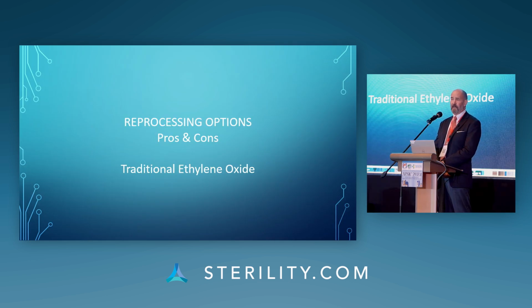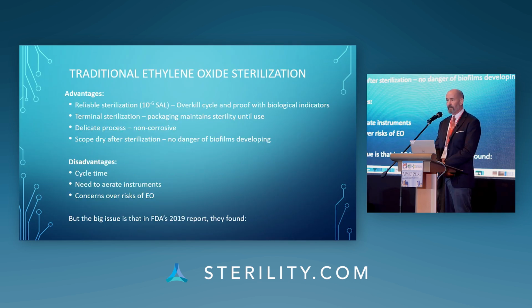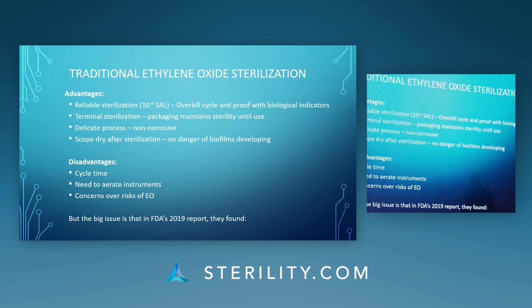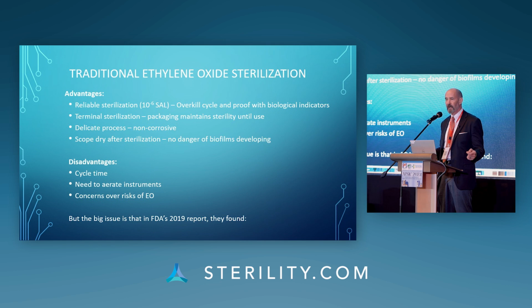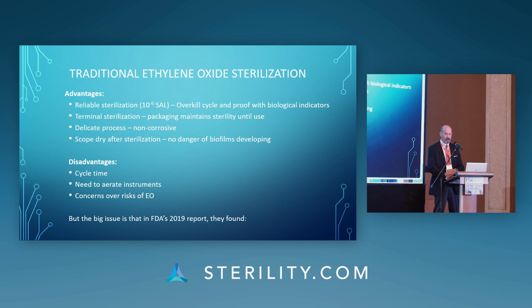Which brings us back to ethylene oxide. The advantages of ethylene oxide are well known. It is, in many ways, one of the most reliable sterilization technologies available. In the United States today, more than 50% of all new medical devices are still sterilized with ethylene oxide, and this is because of the broad material compatibility of the gas. Again, it's a terminal sterilization process. There are a wide range of packaging materials that are compatible with ethylene oxide. It's a very delicate process.